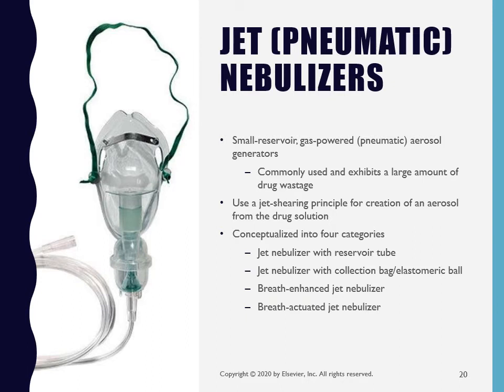As the liquid enters the gas stream, droplets are formed from gas turbulence and impaction on baffles inside the nebulizer. Smaller particle sizes are emitted after the baffling process. Larger particles are recirculated back into the reservoir. There is significant evaporation of solution with gas-powered nebulization.